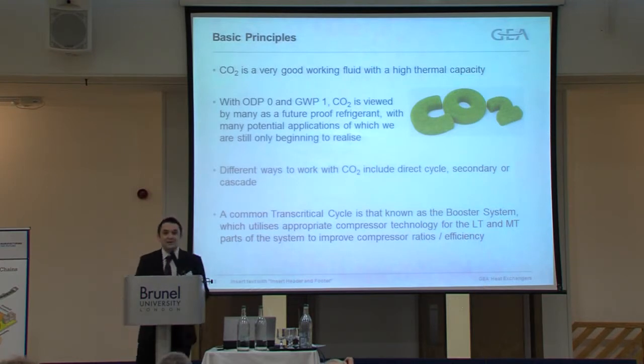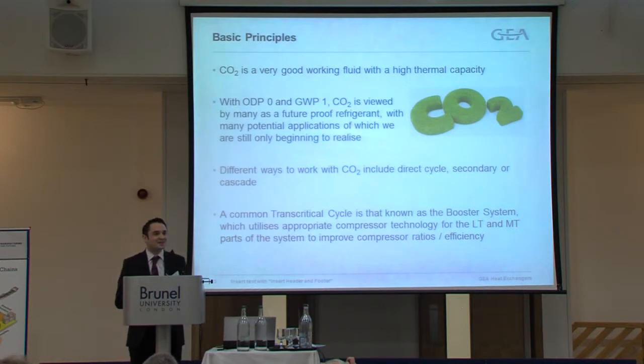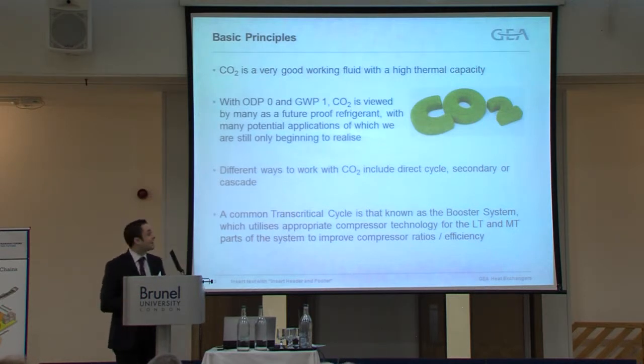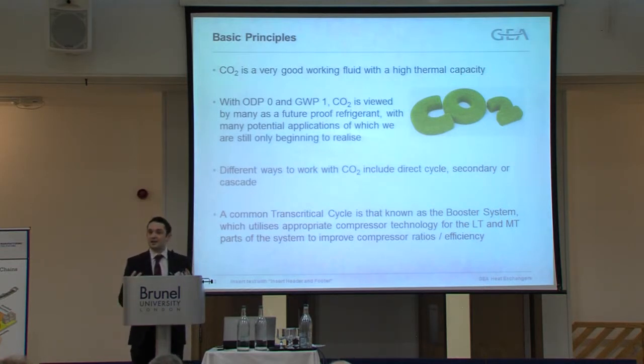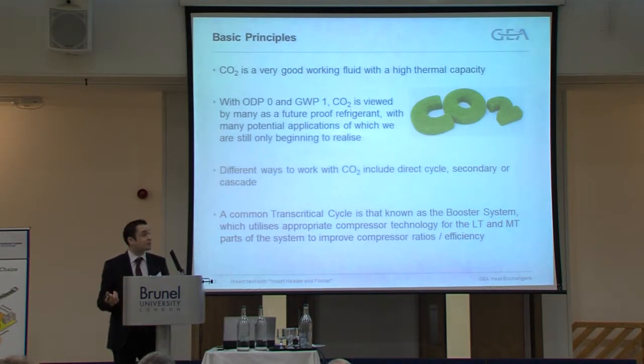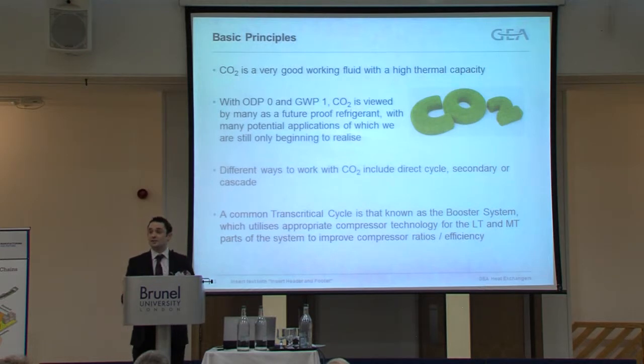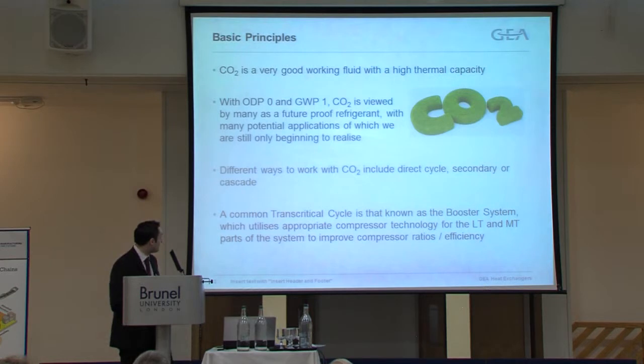Okay, very quickly, we're all here today because we have an interest in CO2 as a refrigerant. I don't need to tell you about the environmental credentials. Sometimes it's overlooked what a good working fluid it is, very high thermal capacity. There are a number of different ways to work with CO2 as a refrigerant: direct cycle, otherwise known as transcritical, secondary or cascade. I'm only going to be talking to you about direct cycle today because that's where the gas cooler is applied.